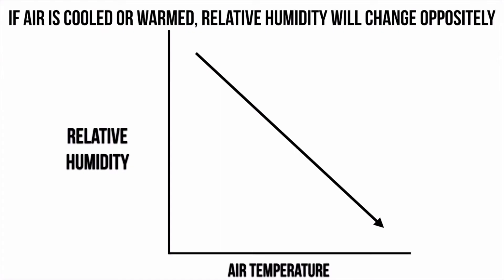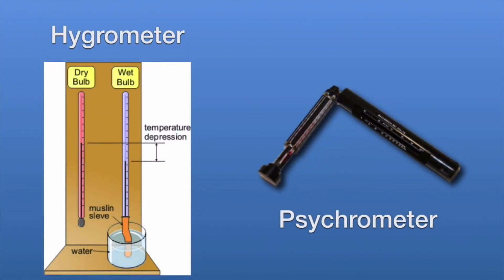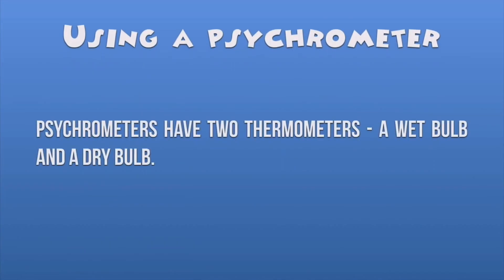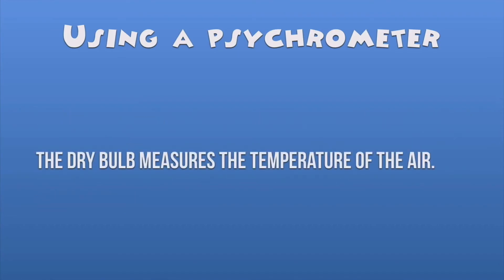To measure humidity we use two devices. One is called a hygrometer, which we won't use. The other is called a psychrometer. A psychrometer uses two different thermometers: one called a wet bulb and the other a dry bulb. The wet bulb is moistened with water and measures the rate of evaporation in degrees — the more water that evaporates from the wet bulb, the lower the temperature will be. The dry bulb simply samples the air.